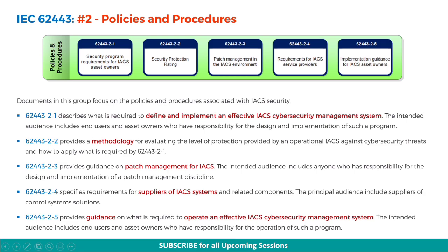The second section is Policies and Procedures, that is 62443.2. Documents in this group focus on the policies and procedures associated with IACS security. 62443.2.1 describes what is required to define and implement an effective IACS cybersecurity management system, intended for end users and asset owners. 62443.2.2 provides a methodology for evaluating the level of protection provided by an operational IACS against cybersecurity threats. 62443.2.3 provides guidance on patch management, intended for anyone responsible for the design and implementation of a patch management discipline.